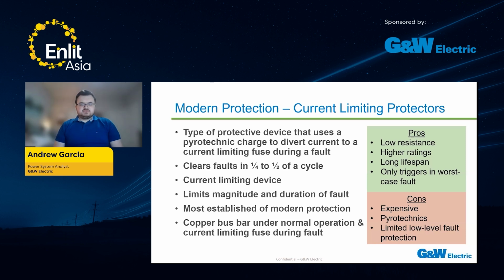This technology has been established for over 40 years, so it's the most established of these modern protective devices on the market. And it's very low resistance. It's a copper bus bar in normal operation. That's a copper bus bar lined with those pyrotechnic charges, and it becomes a current limiting fuse during a fault, after the pyrotechnic charge activates and diverts all that current to the current limiting fuse. So there are a lot of pros to these devices. They're very low resistance. Basically, you'd have the same amount of resistance as you would in a chunk of copper bus bar, which is negligible.